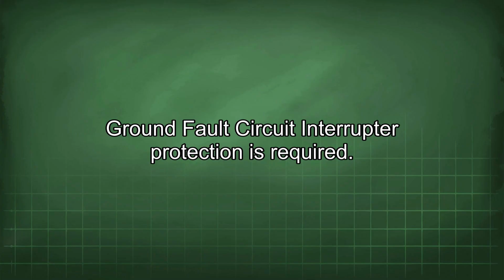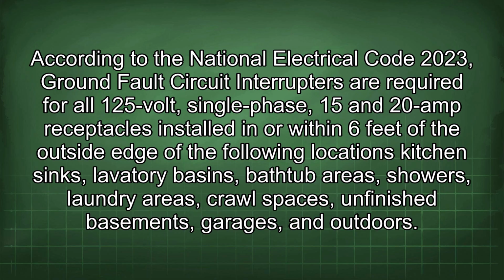Ground fault circuit interrupter protection is required. According to the National Electrical Code 2023, ground fault circuit interrupters are required for all 125-volt single-phase 15 and 20 amp receptacles installed in or within 6 feet of the outside edge of the following locations: kitchen sinks, lavatory basins, bathtub areas, showers, laundry areas, crawl spaces, unfinished basements, garages, and outdoors.